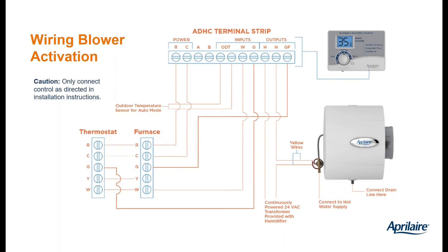So in this diagram, we're coming out of one of the H's, we're going to one of the yellow wires on the humidifier, coming out of the other yellow wire on the humidifier, going into one side of the 24 volts of the transformer, and then the remaining screw head terminal on the transformer, we're running back up to the last H terminal. So that's simple, straightforward. And that just leaves 2 terminals.